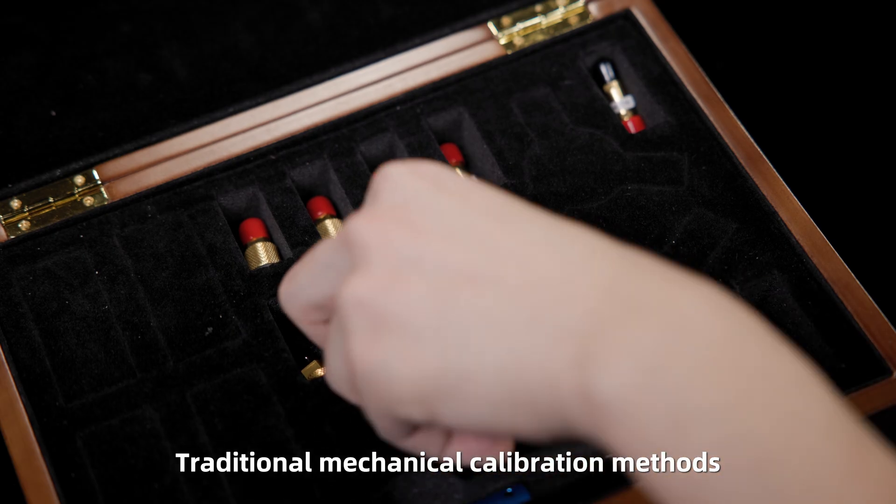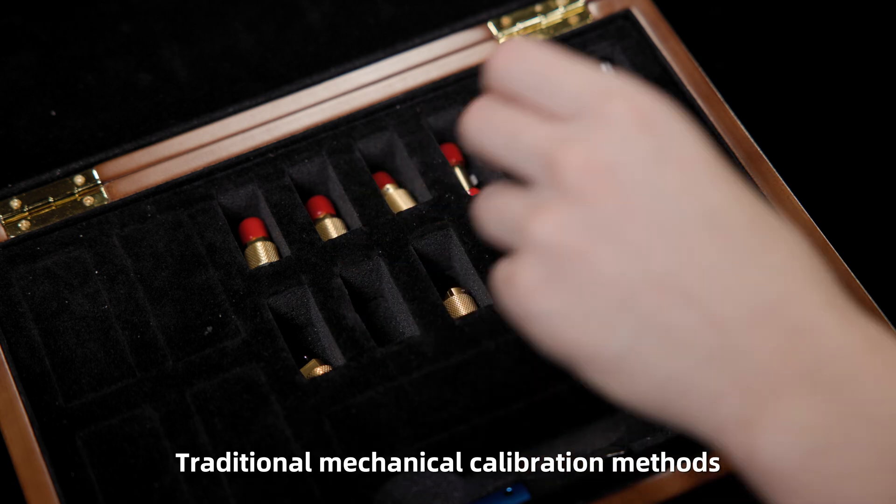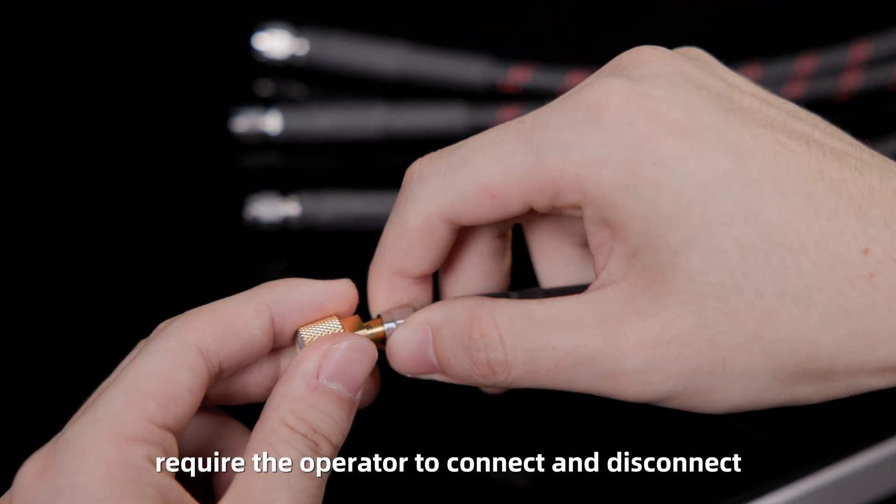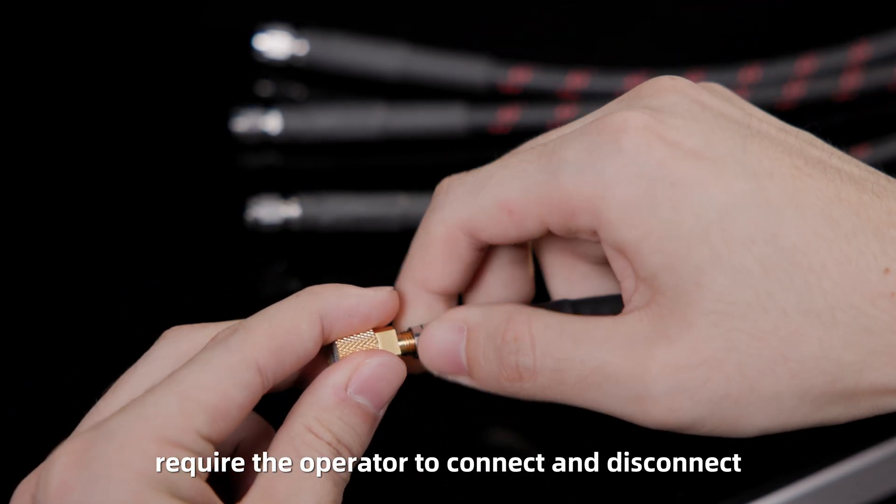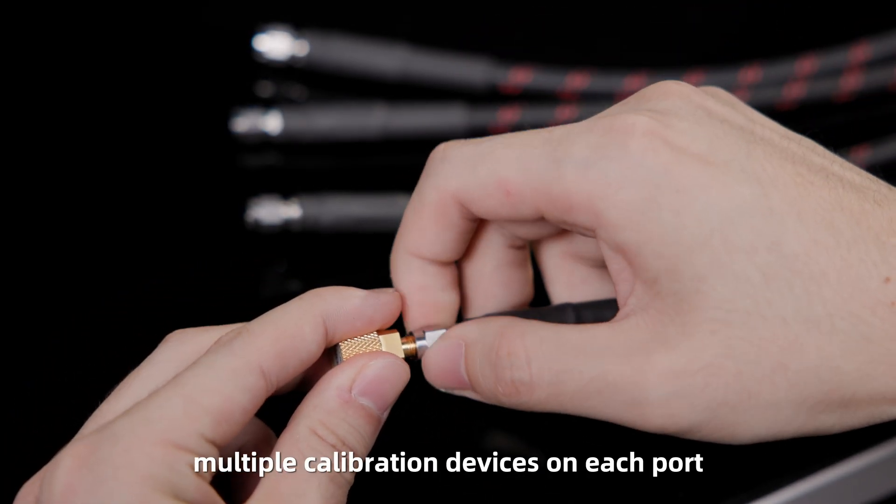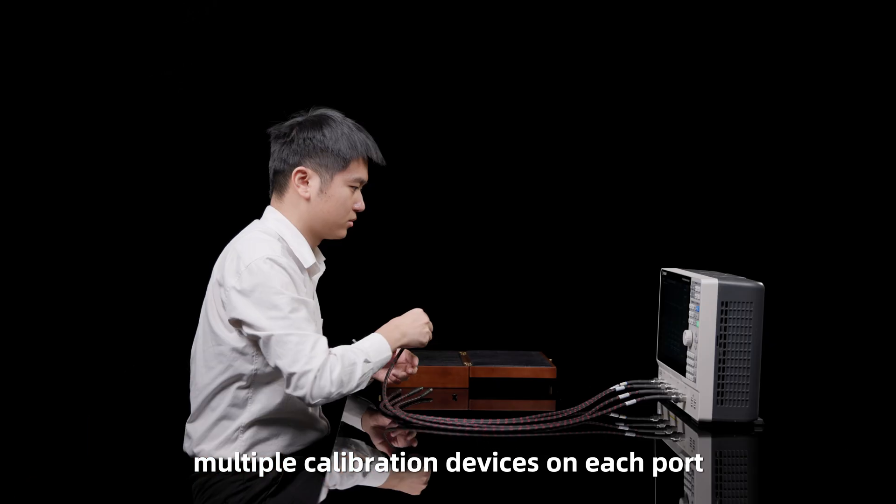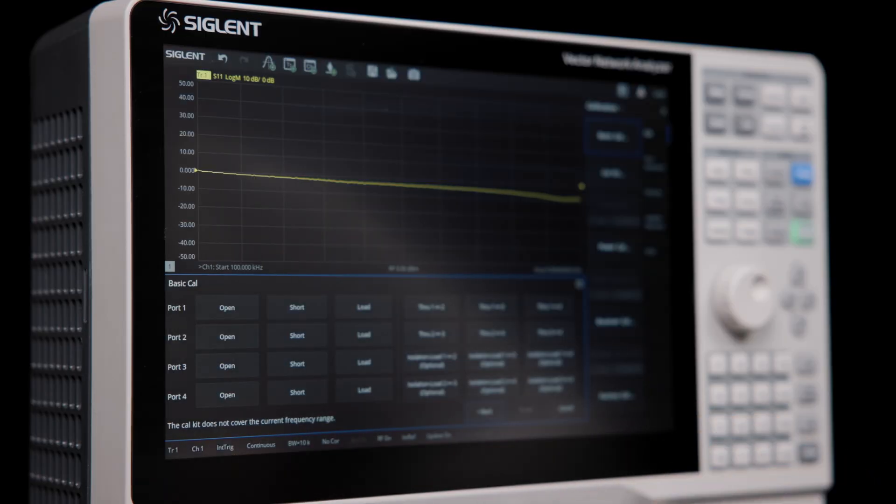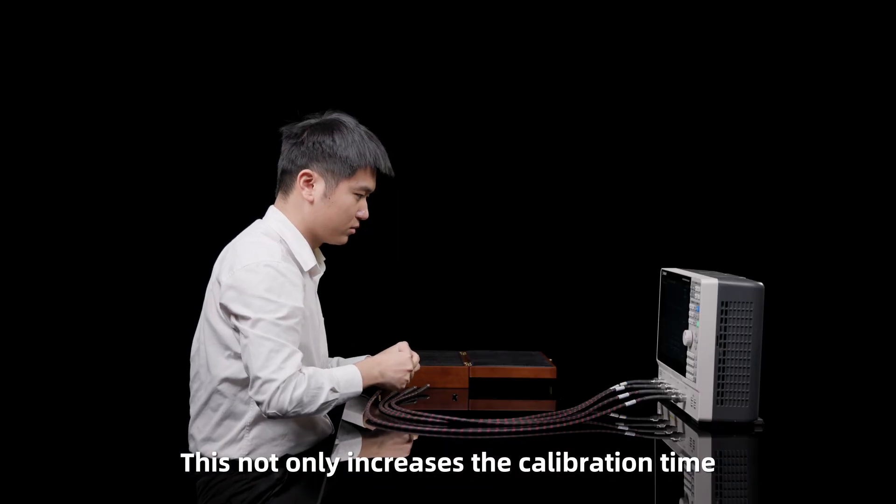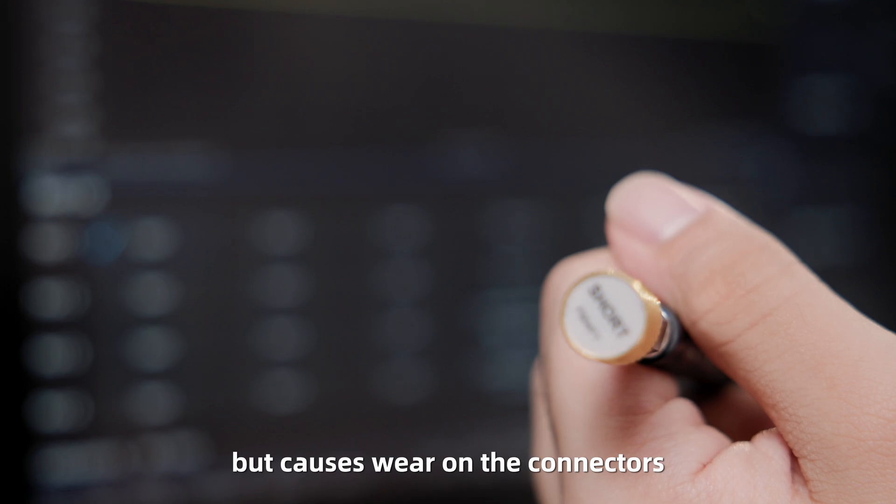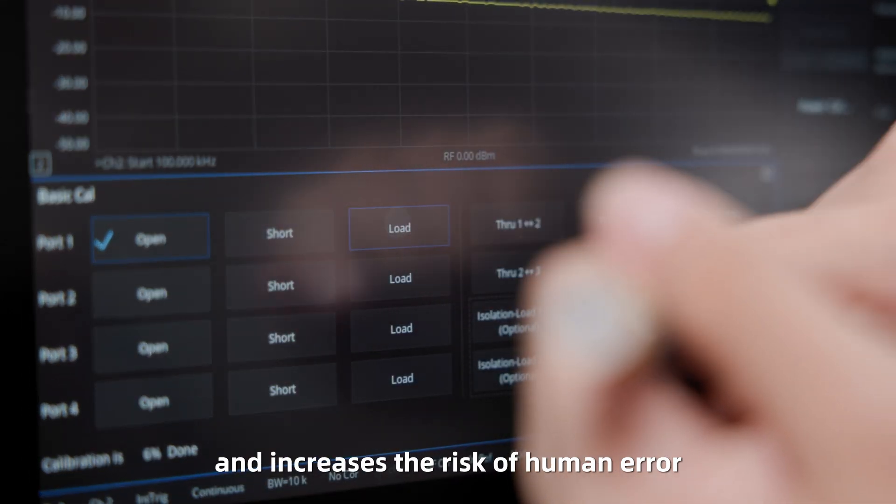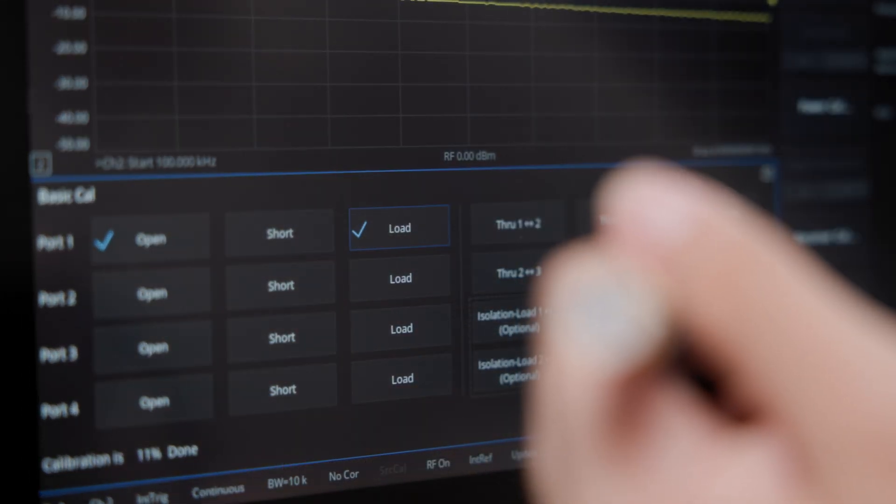Traditional mechanical calibration methods require the operator to connect and disconnect multiple calibration devices on each port. This not only increases the calibration time, but causes wear on the connectors and increases the risk of human error.